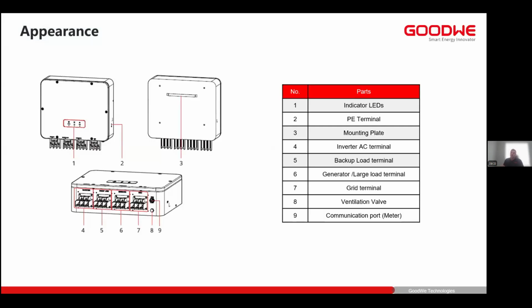We can also see that there are some indication lights on the front of the unit, and that will give you a good understanding of the state of the inverter and the state of backup, directly by just looking at the STS. Then there are the various AC terminals. So that's the inverter AC terminal, the backup load terminal, generator or large load, and then the grid terminal. That's where all the AC connections will be connected. The only other thing that needs to be connected between the STS and the inverter is a communication cable. So there's also a communication port that will enable that.